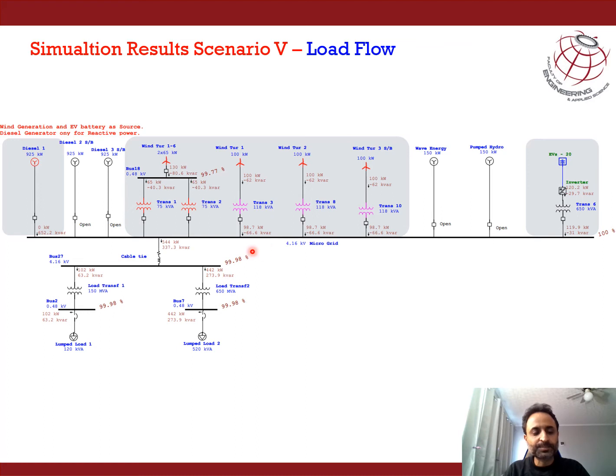In this case, you can see that the active power generation from the diesel generator has been reduced to zero. The complete active power is being met by the wind turbines and the electric vehicles. The reactive power requirement of the wind turbines and the load is met by the diesel generator, because in this case the diesel generator is the only prime source of reactive power. So in this case, we have to keep the diesel generator connected only for supplying reactive power to the grid. This simulation basically shows that, in case the diesel generator is supplying in addition to the renewables, EVs can increase the stability of the system by providing a large amount of power surge for a short duration of time. In this case also, we were successfully able to maintain the voltage at the load bus.